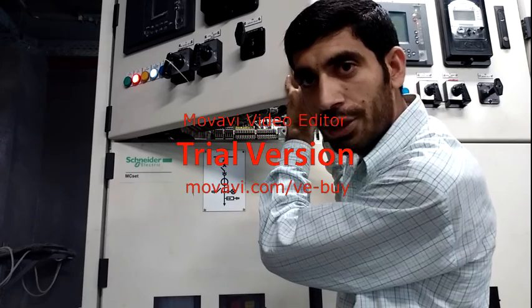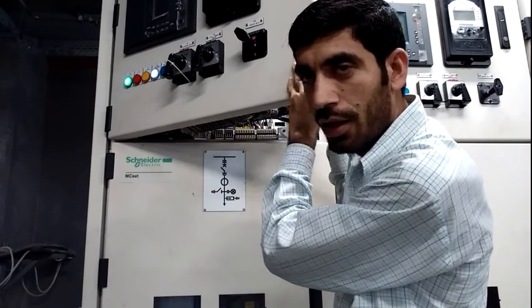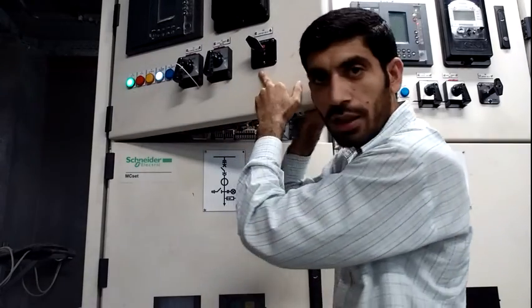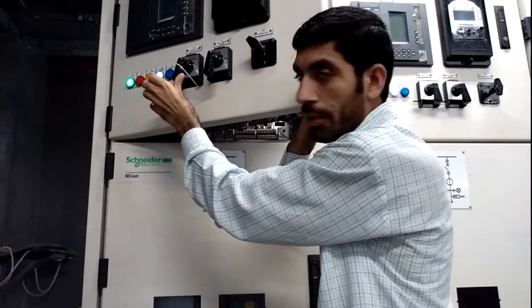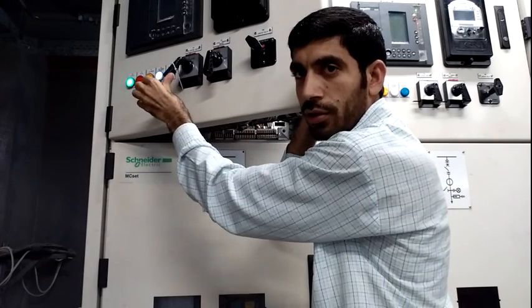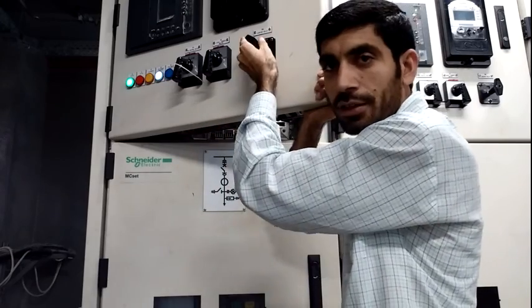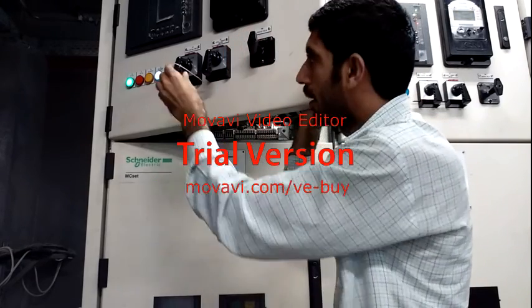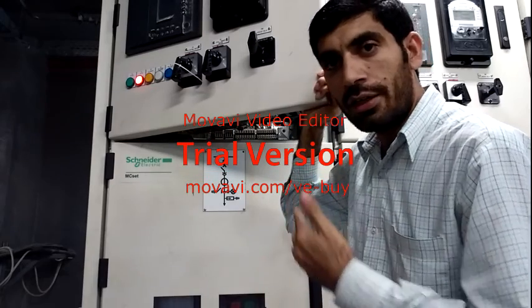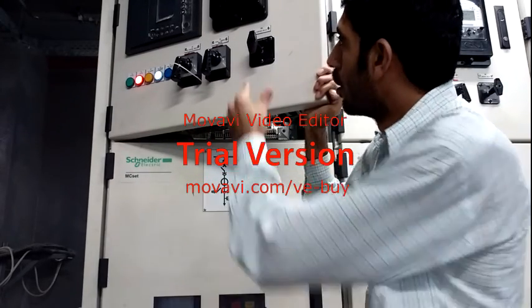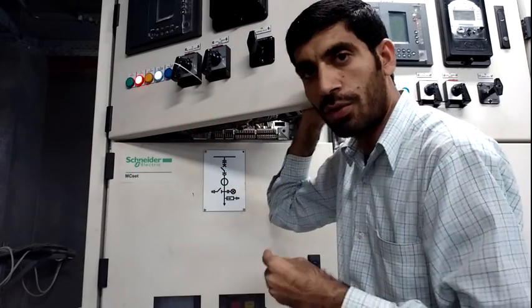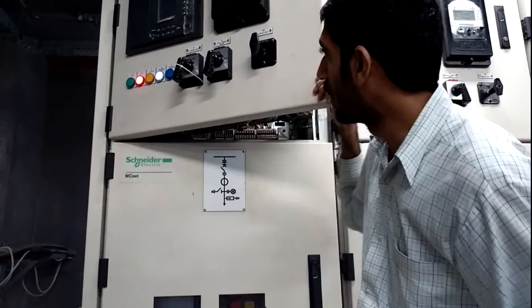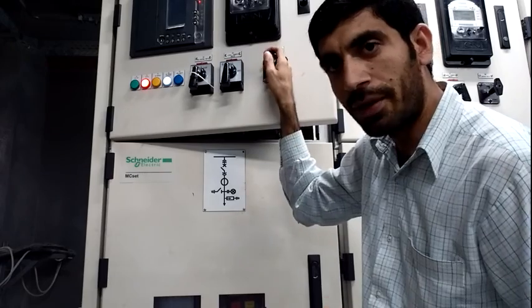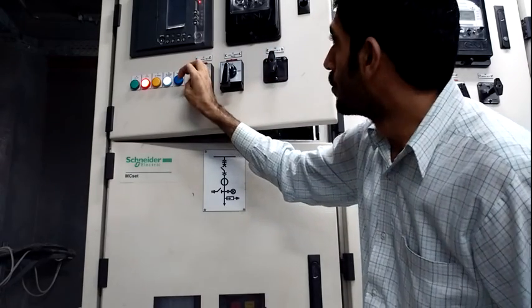Through local or remote, in both conditions I cannot close the breaker. Now the breaker is open and the lockout is also operated, so I cannot reclose the breaker. When I reset the lockout, I can close. So this is the interlock. This is the lockout condition. This is how to operate the lockout relay. When the lockout relay is operated, I cannot close the breaker.